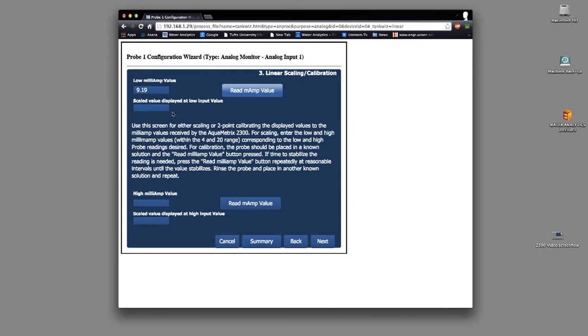The calibration screen also allows you to enter manually a calibration value instead of taking a live measurement. This is very useful for transferring a previously done calibration to a new probe setup, or when only one calibration point is available. Now, as I wait for the probe reading to settle down, I'll type in the value of the calibration standard. In this case, it's pH 4.